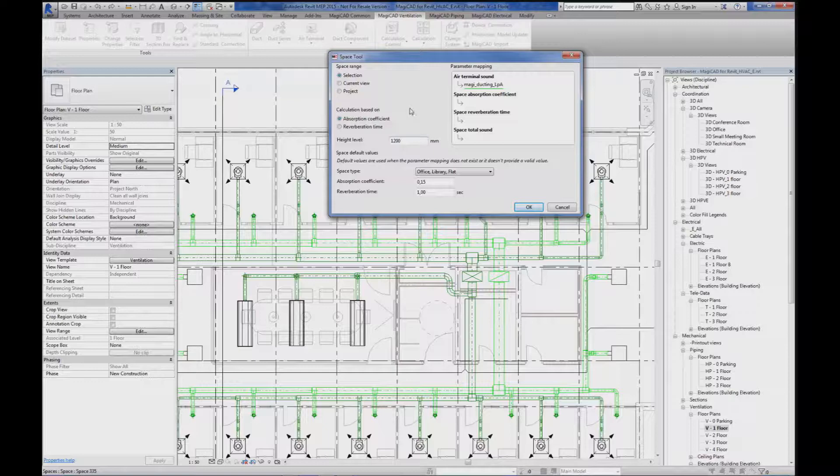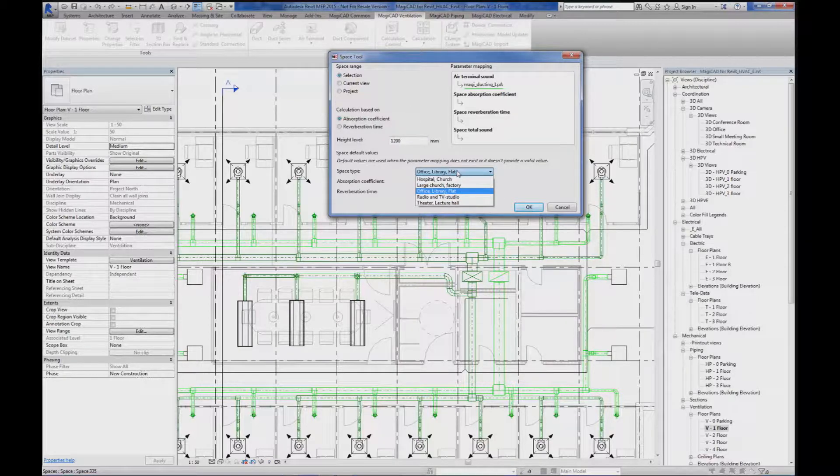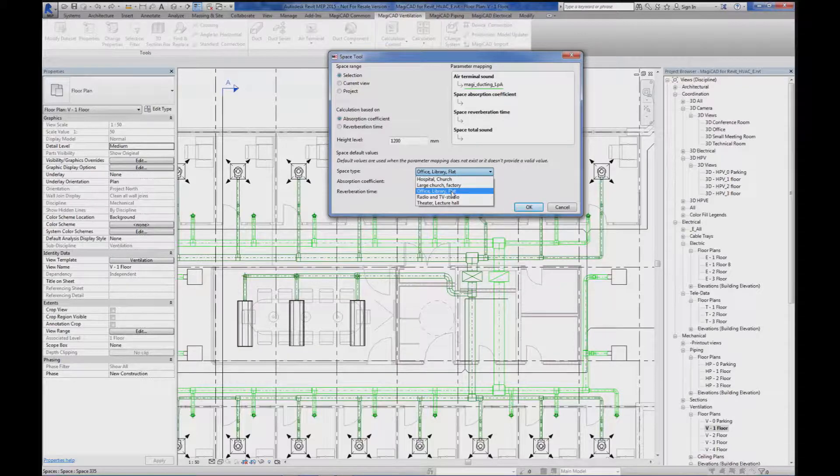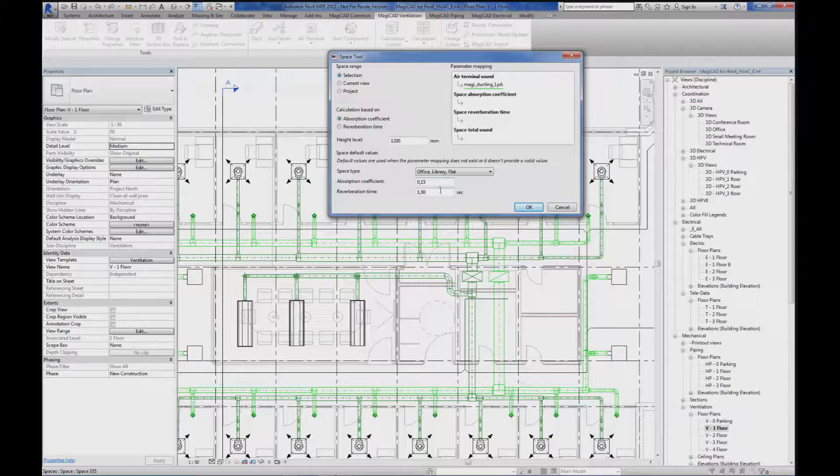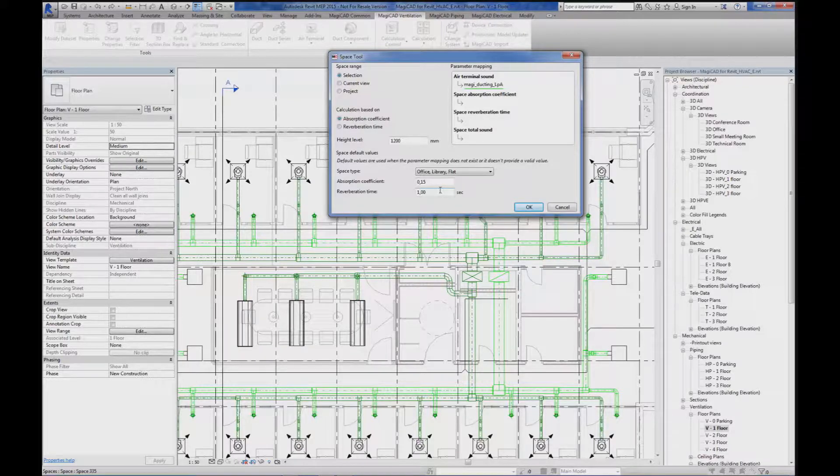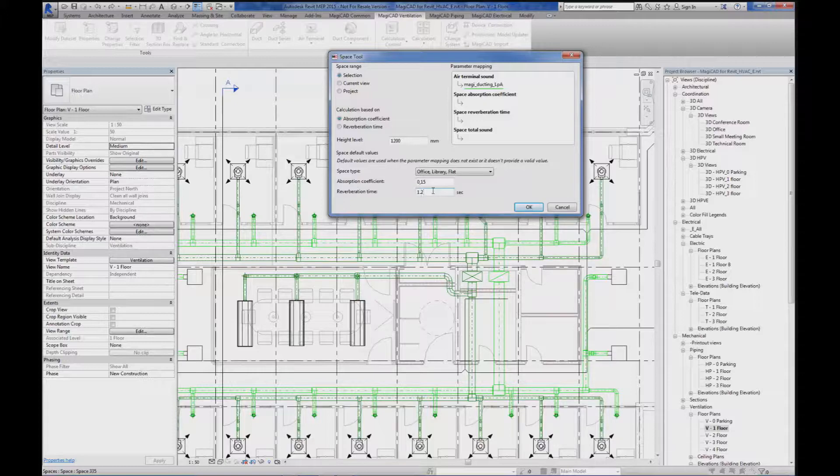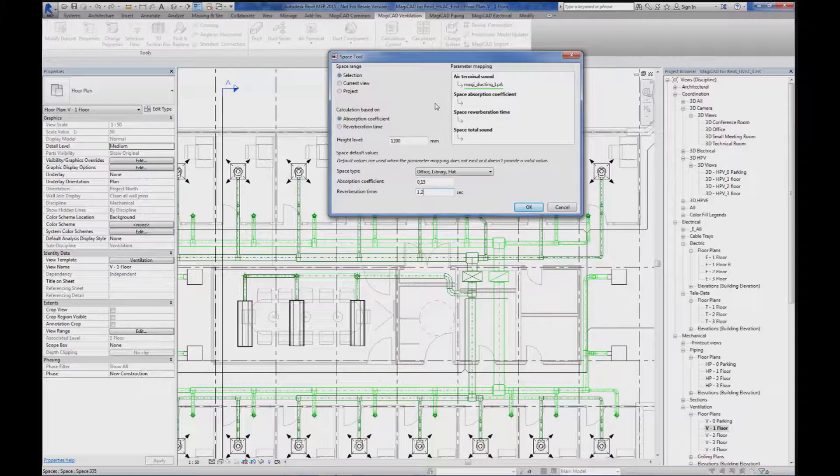The input for the parameters can be done either by selecting in the drop-down list a suitable room type that automatically fills in the absorption coefficient and the reverberation time, or you can enter the reverberation time by yourself. Another option is to actually read the parameters from the spaces if you already have the parameter for absorption coefficient, reverberation time or air terminal sound in the space.